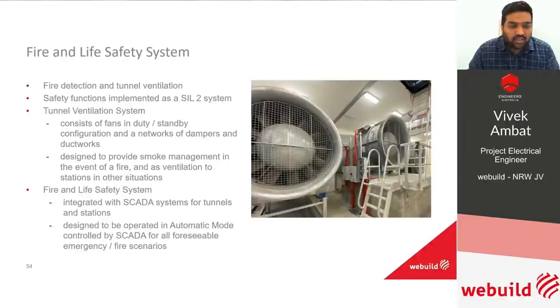The tunnel ventilation system consists of a number of fans at the portals and the two underground stations, arranged in a duty standby configuration, along with a series of dampers and ductwork. Overall it's designed to provide two functions: smoke management in case of a fire scenario in either the tunnel or the stations, and in 99% of the time in other situations, ventilation for station comfort for passengers and everyone else.